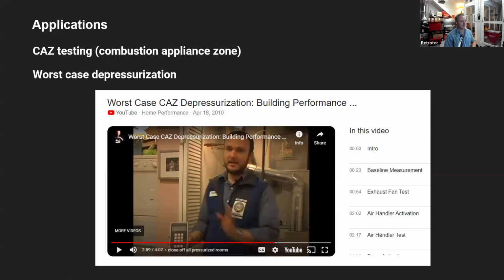Took a screenshot here from one of Corbett Lunsford's videos, doing some CAZ testing, or combustion appliance zone testing. So if you're doing a worst case depressurization test in a house, a lot of our friends in weatherization do this. Basically, if you have a gas water heater and you want to see if you can set the house up to where you can make it backdraft, you can do that.